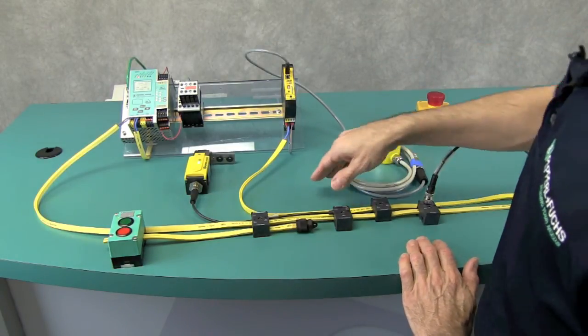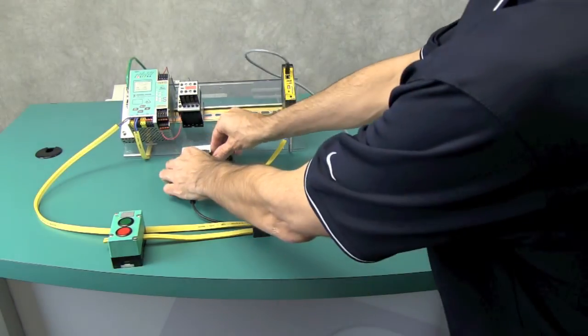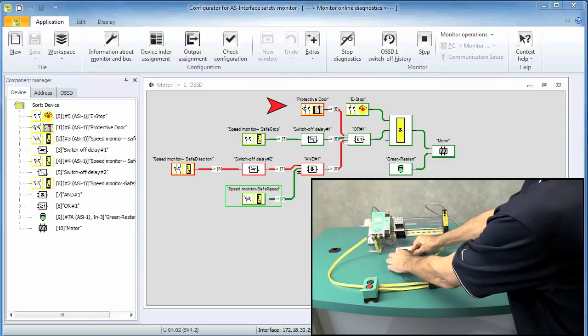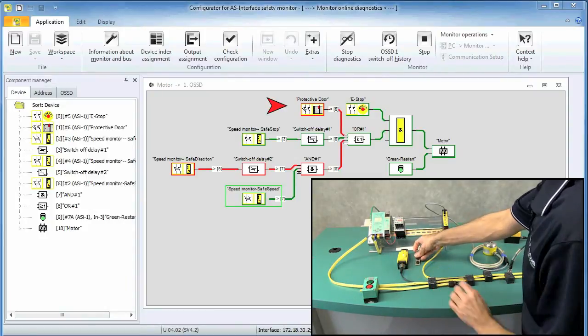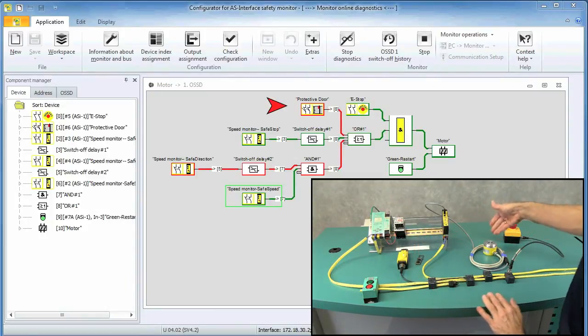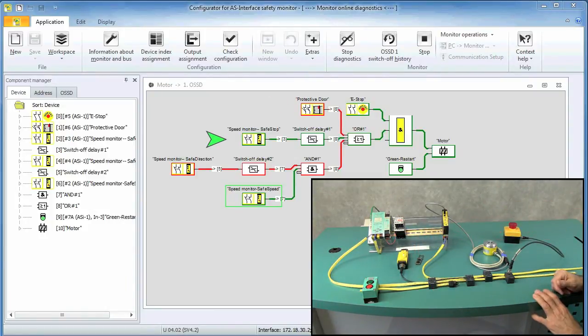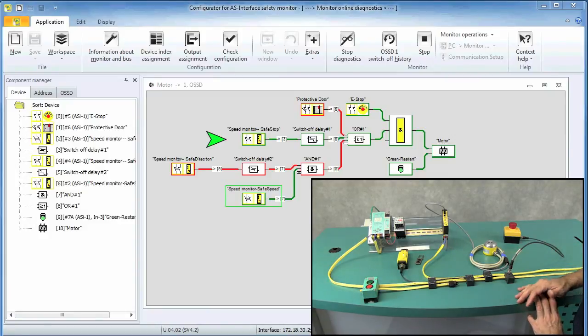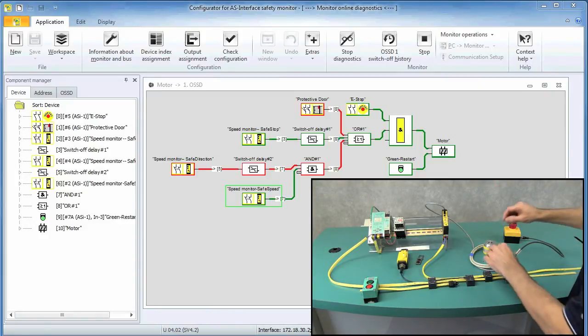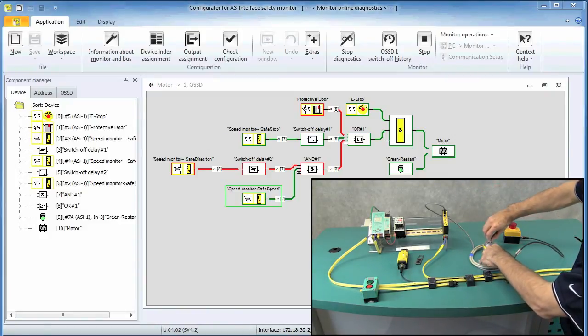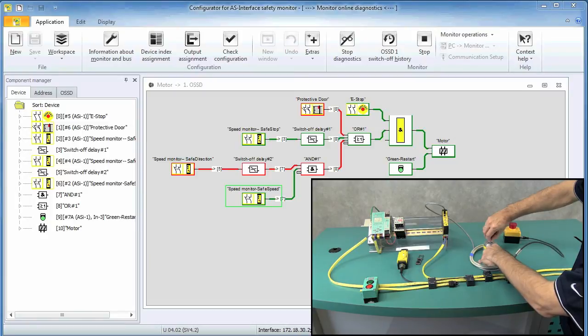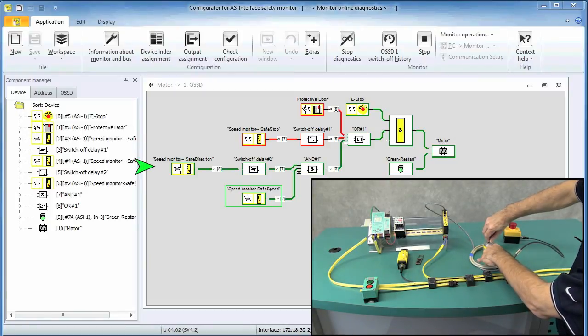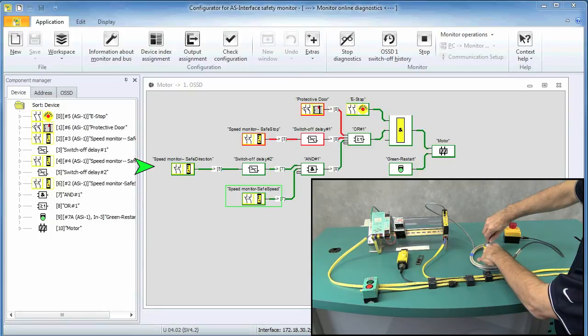Let's then go and assume that maintenance gains access to the system. As long as the press is not moving, this will not shut down the system so the contactor is still closed. Now we will command the motor to turn slowly and expect that the contactor remains closed.